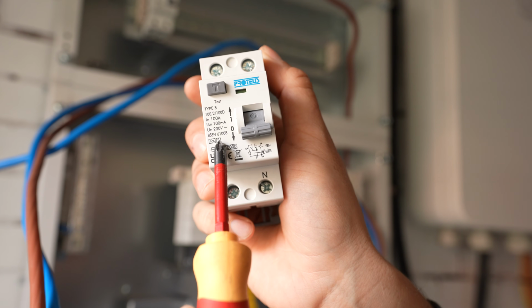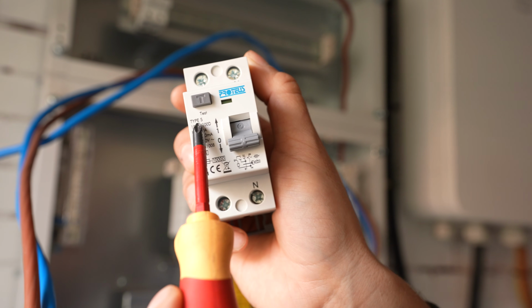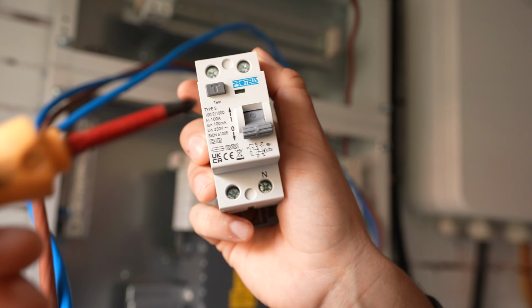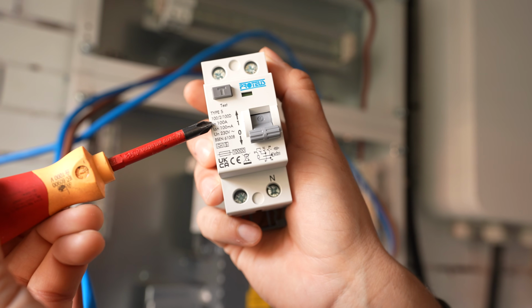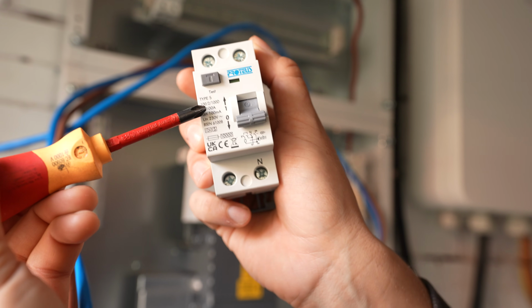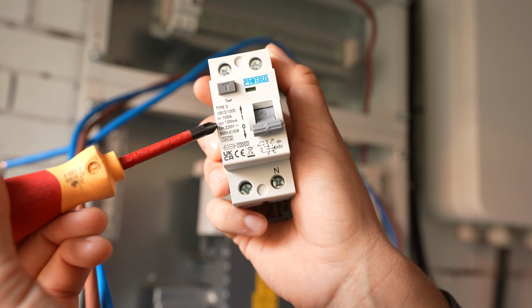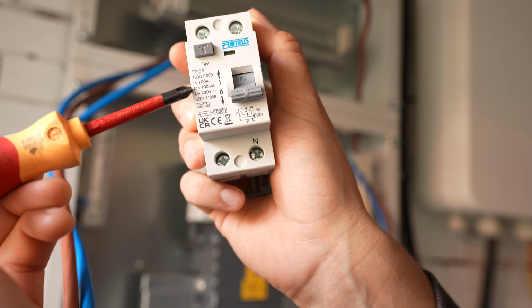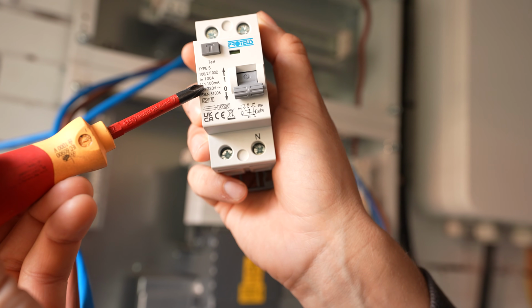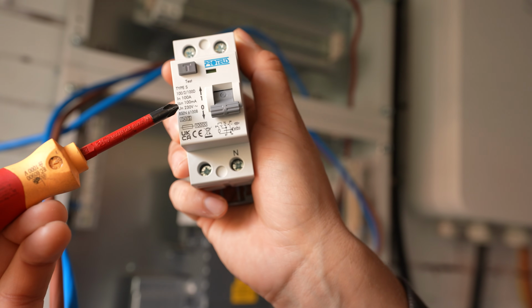And then the little letter S means that this is a type S device, which means there's a time delay. We've also got here our IN, which is our rated device current, which is 100 amps. So it's a 100 amp RCD. And then I delta N, which is our operating current, which is 100 milliamps. So at 100 milliamps this device will operate.